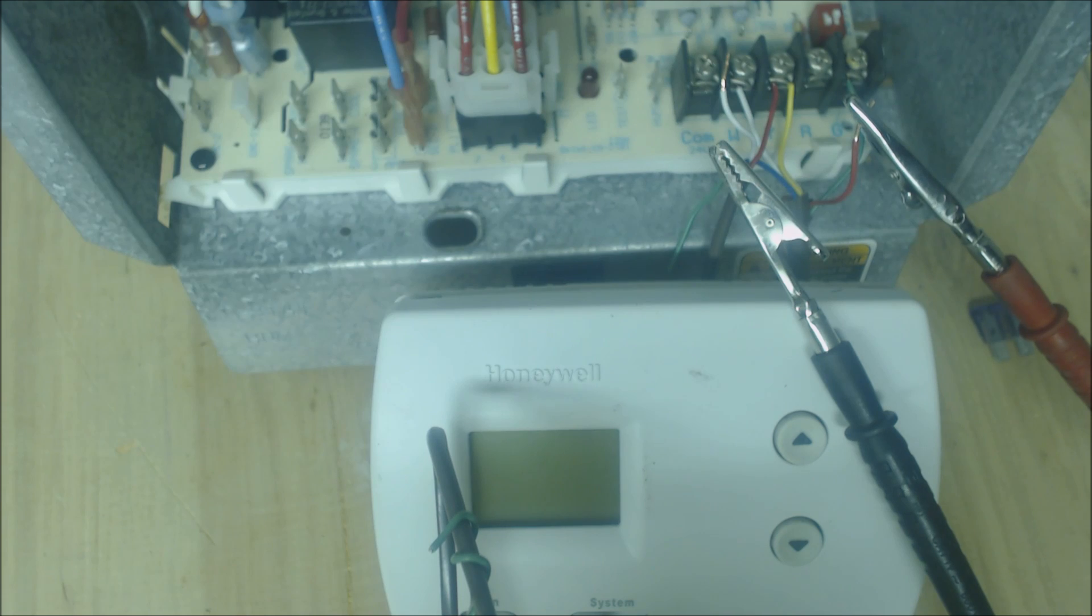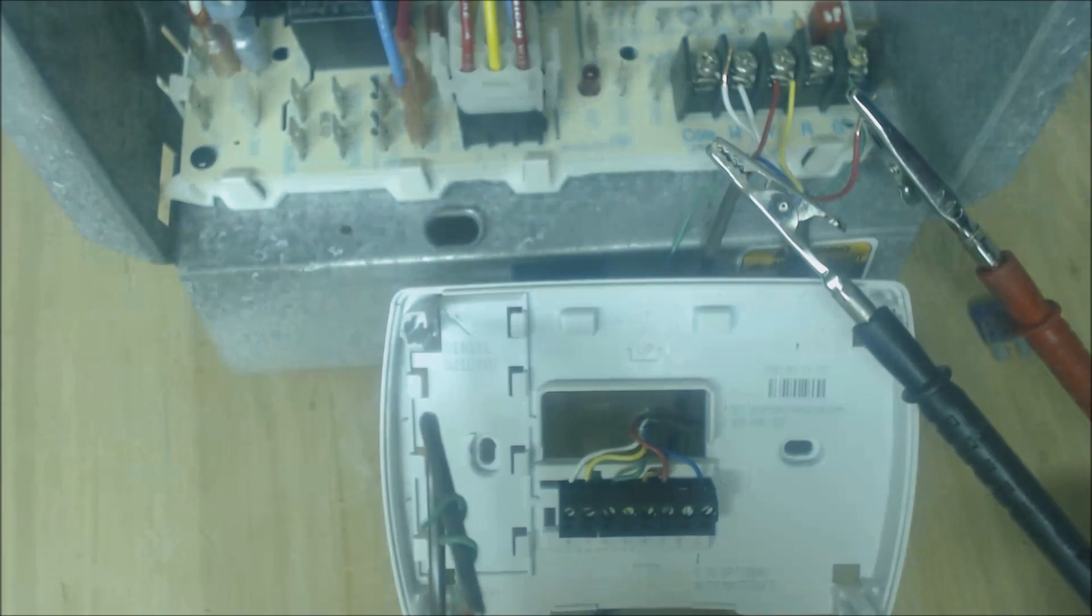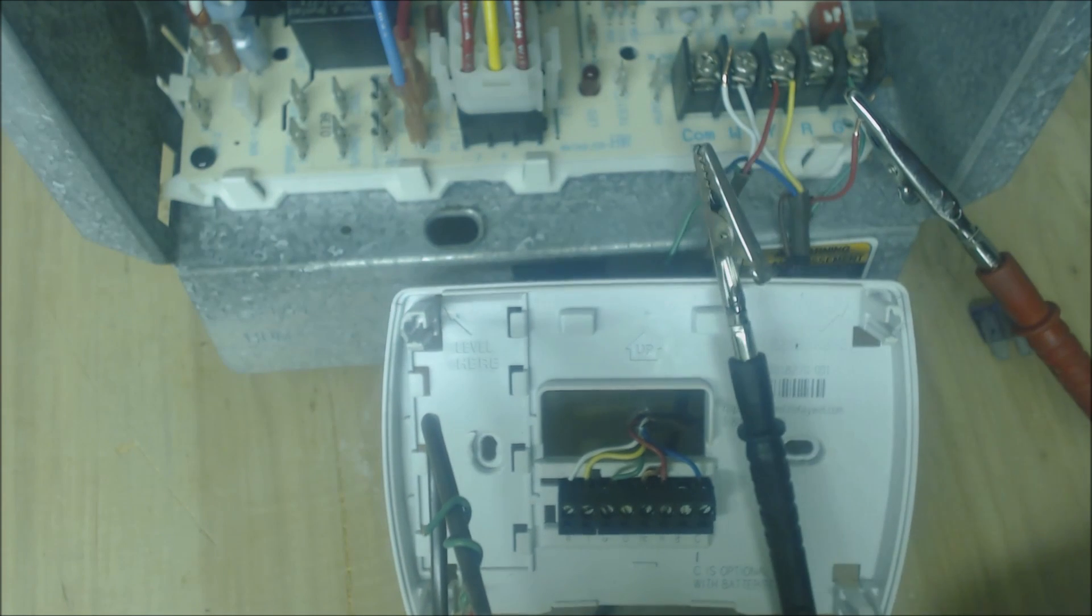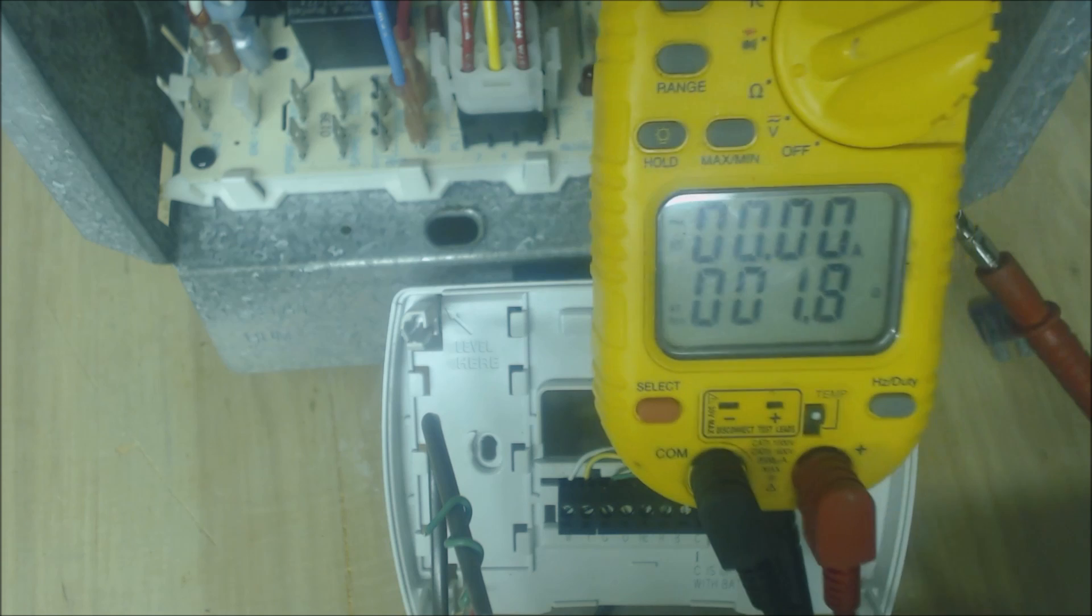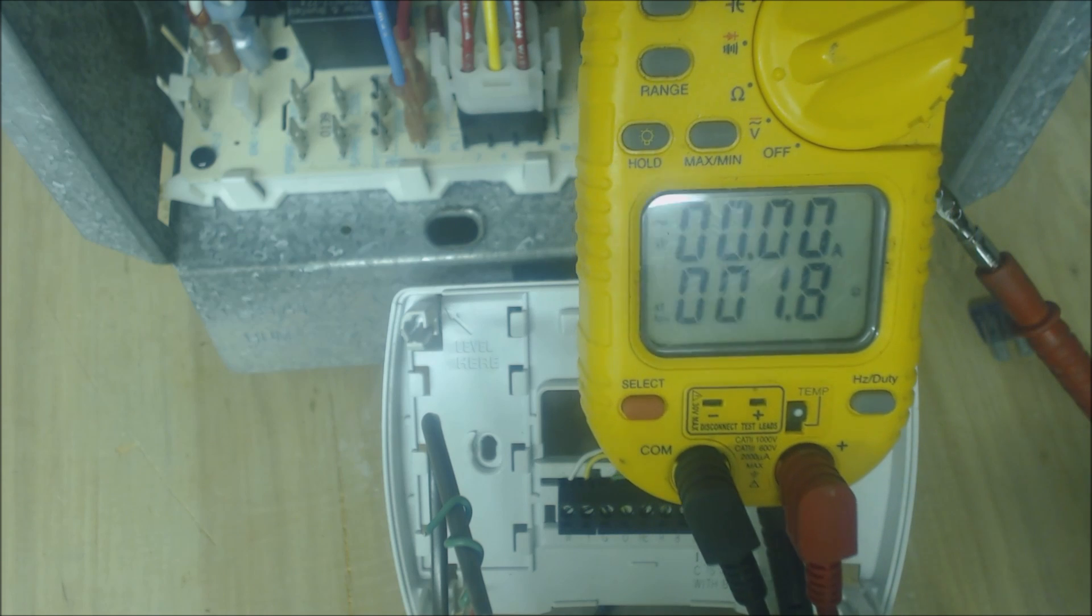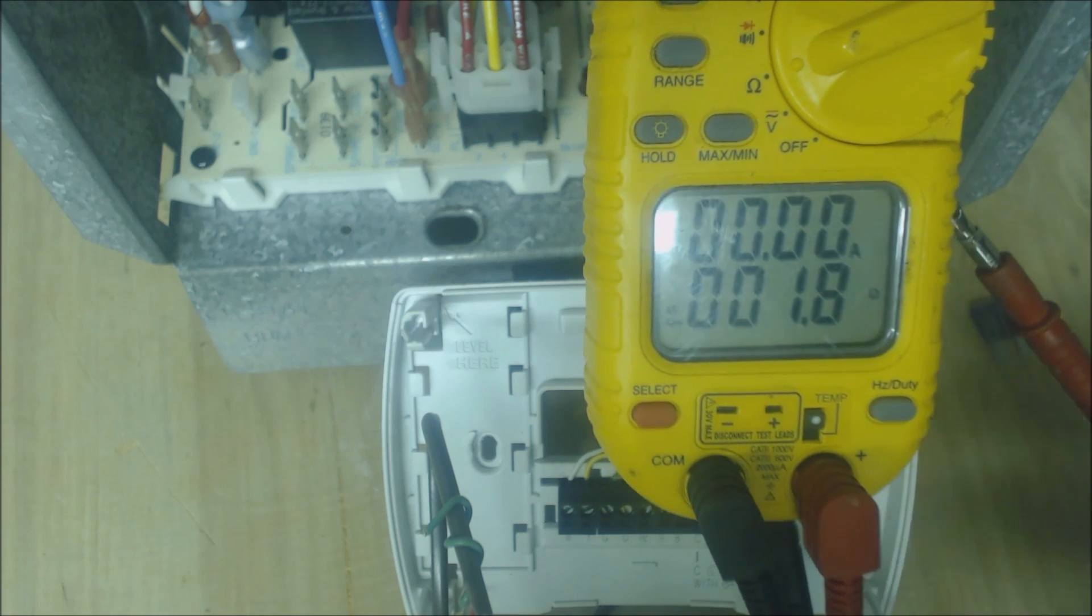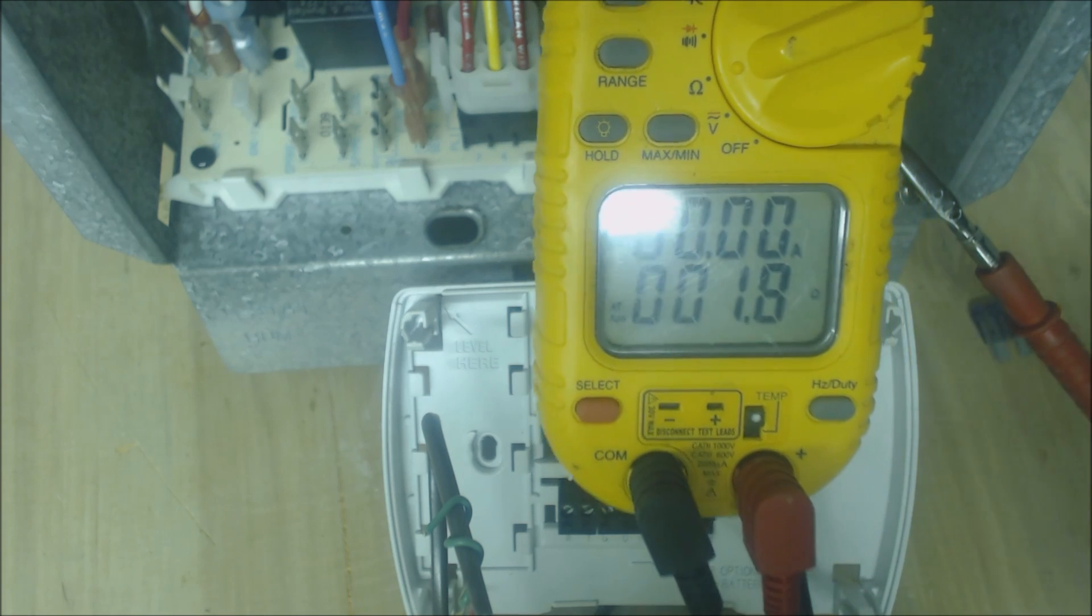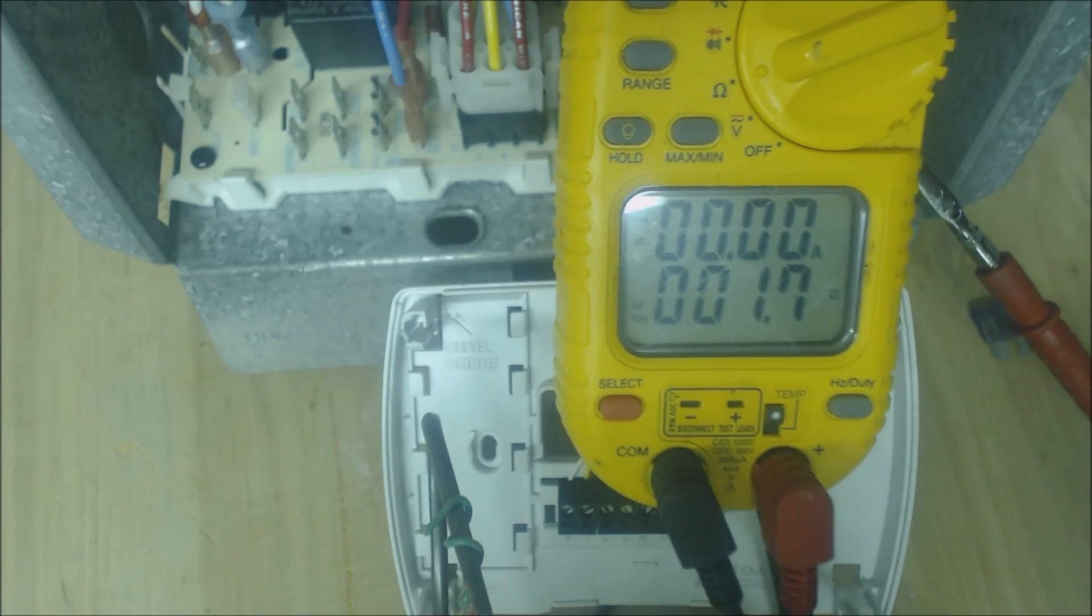The next thing that we're going to do is we're going to remove the faceplate of the low voltage thermostat and then now we're going to check again. It reads 1.9, 1.8 ohms of resistance to electrical flow.